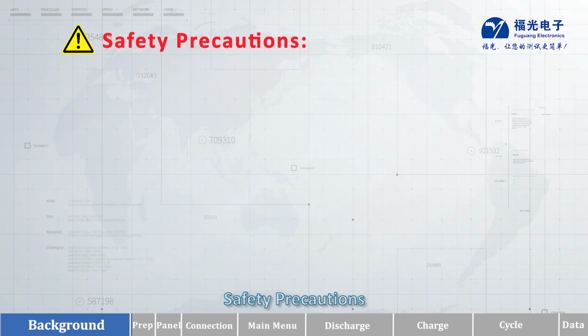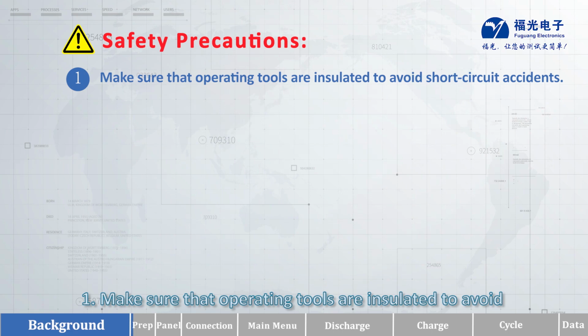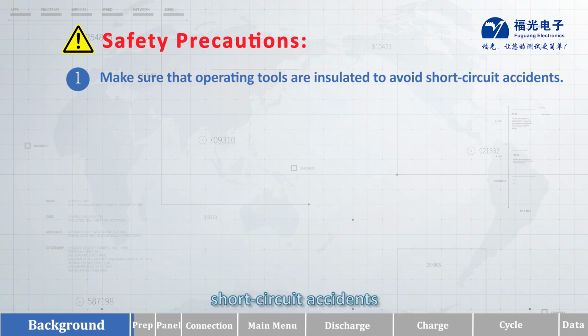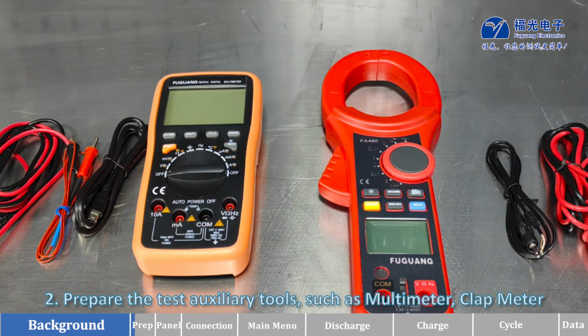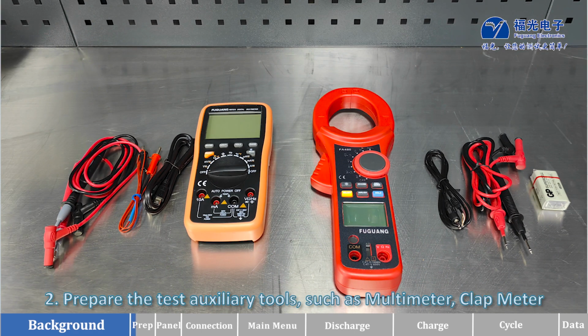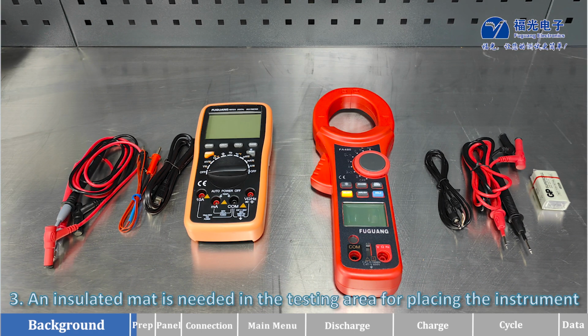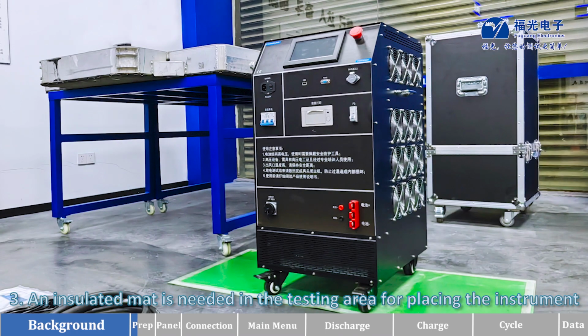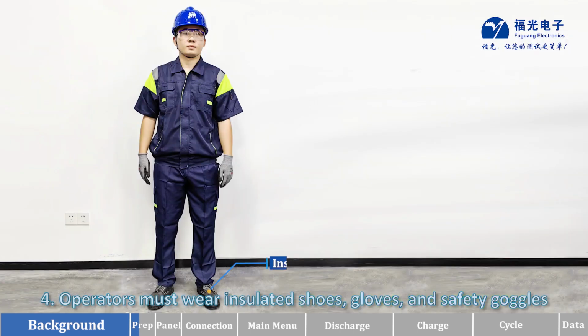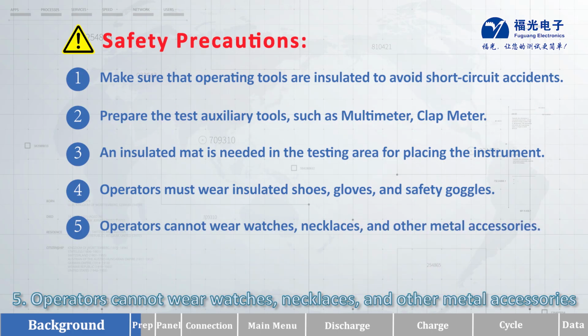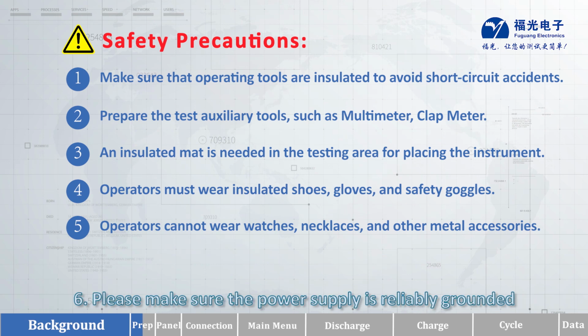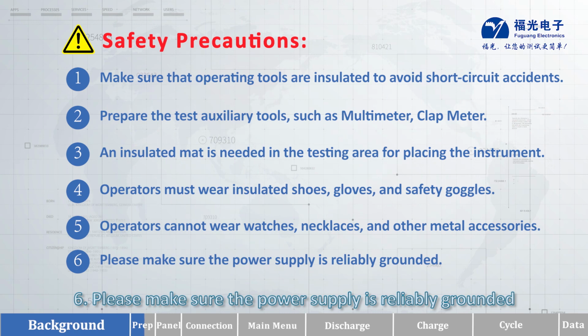Safety precautions. First, make sure that operating tools are insulated to avoid short-circuit accidents. Second, prepare the test auxiliary tools, such as multimeter, clamp meter. Third, an insulated mat is needed in the testing area for placing the instrument. Fourth, operators must wear insulated shoes, gloves, and safety goggles. Fifth, operators cannot wear watches, necklaces, and other metal accessories. Sixth, please make sure the power supply is reliably grounded.